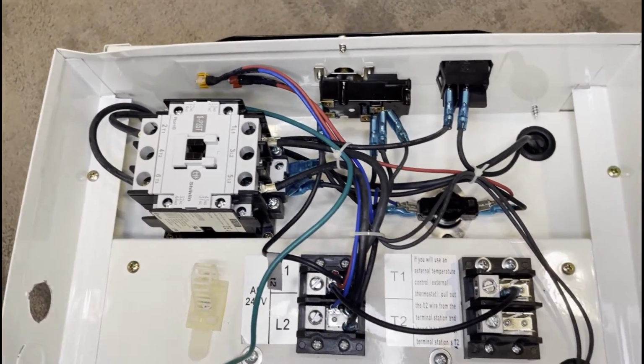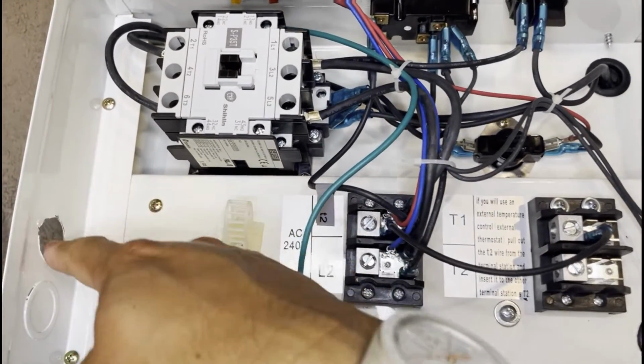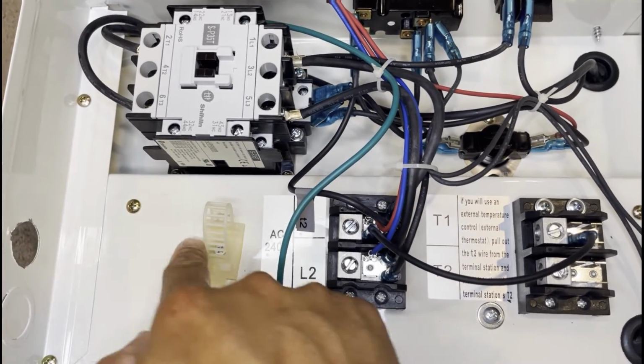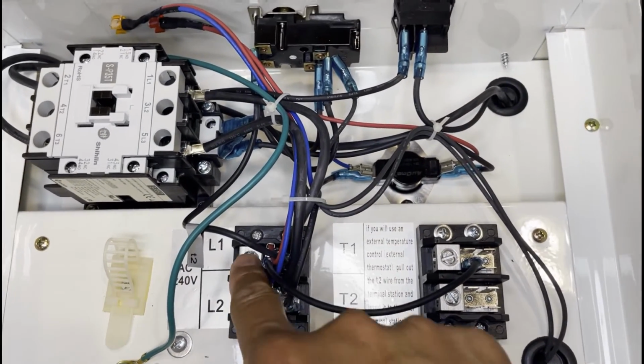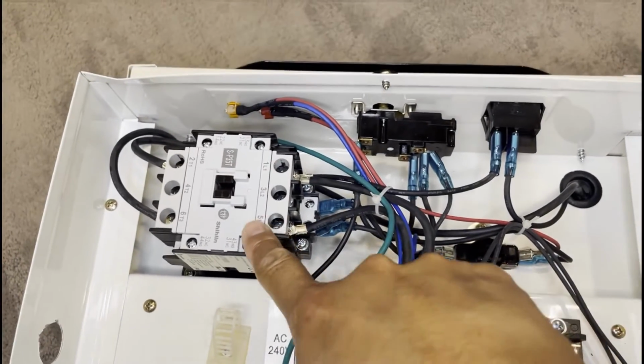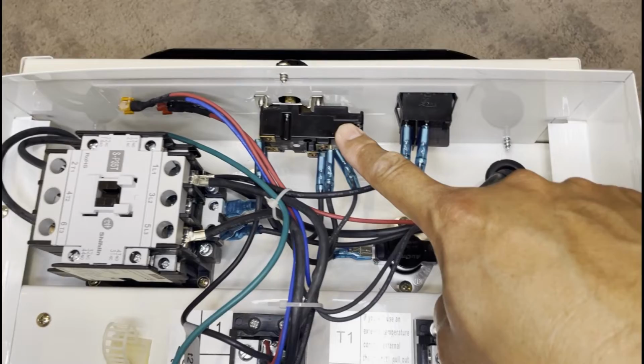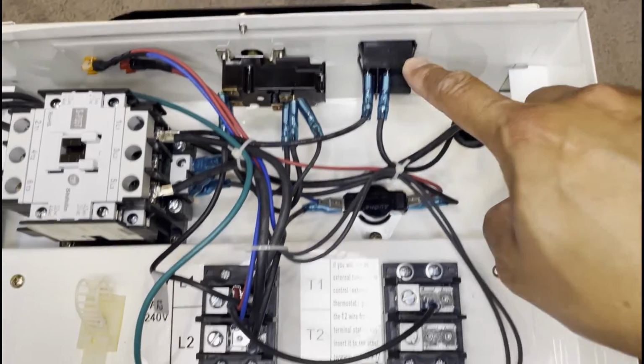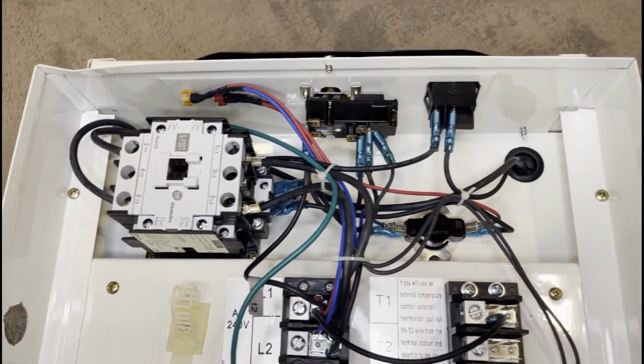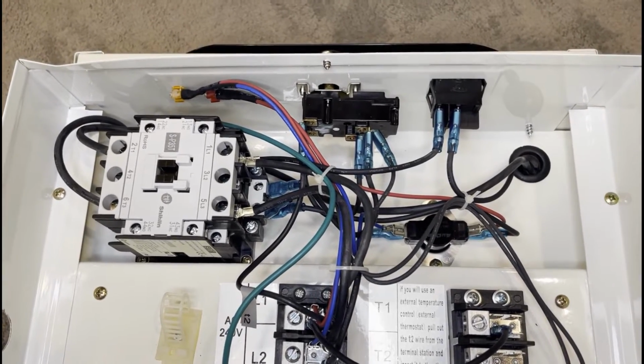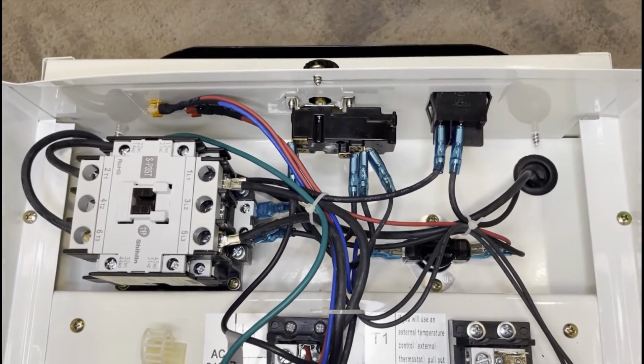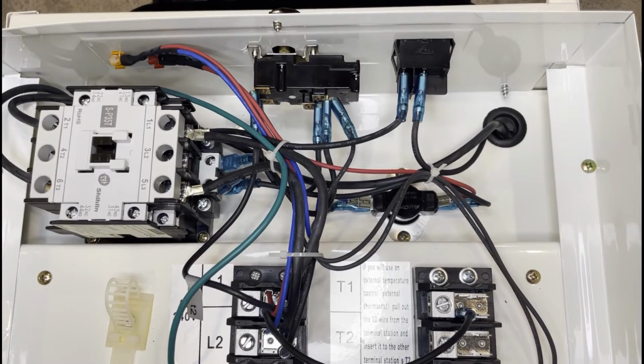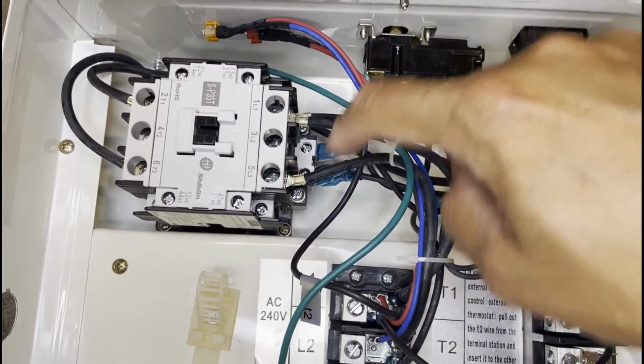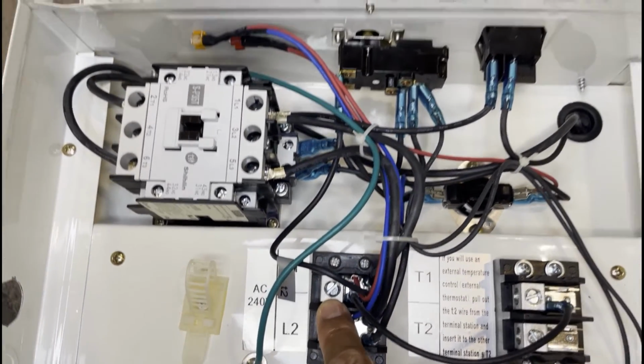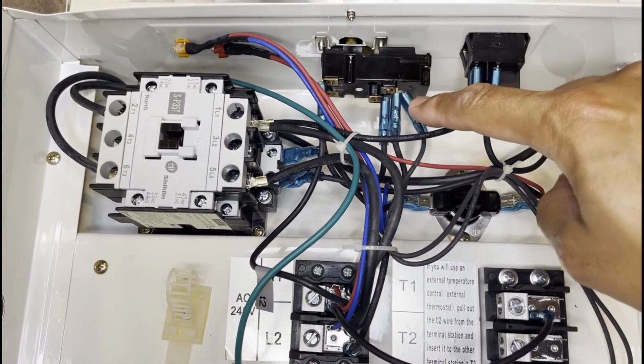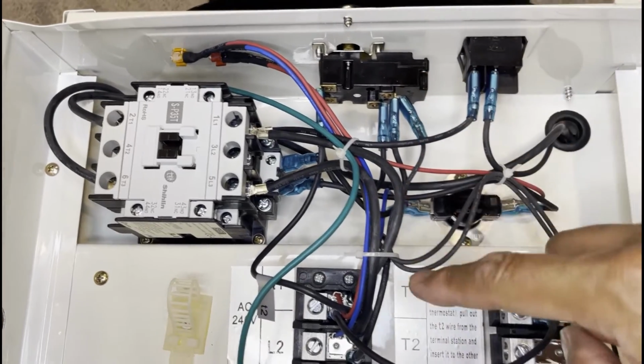So here's the wiring inside our electric heater. So you got your Romex 8 gauge wire coming in here. You got 240 volts, which is then connected to L1, L2 of this terminal. You got your contactor. This is your temperature control thermostat. And then you got your switch, and then this is your limit switch. This particular heater comes with this temperature control thermostat, which has a two connection. One on the left side is connected to L1 of this terminal, and then the other side you got a piggyback connector. One goes to our contactor and the other one goes to our fan motor.